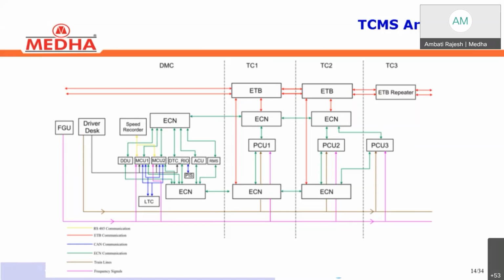And next, there is a speedometer, the speed recorder, in the driver desk. This is also connected with MCU 1 and 2 via RS485 communication for data exchange. And there is an FGU, frequency generator unit, inside the driver desk. From the train control point of view, if communication is healthy, the train works in normal mode. And in case of any problem in communication, the train automatically works in special RDM mode by taking the signal from the FGU. FGU gets the commands from the master controller.